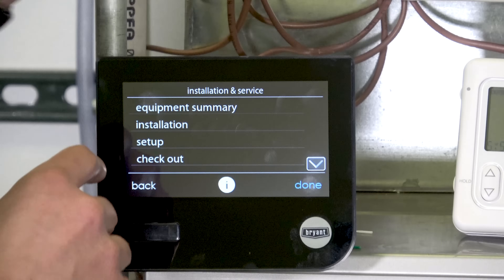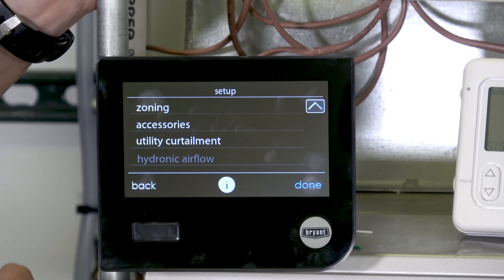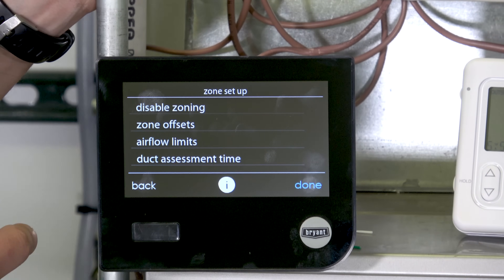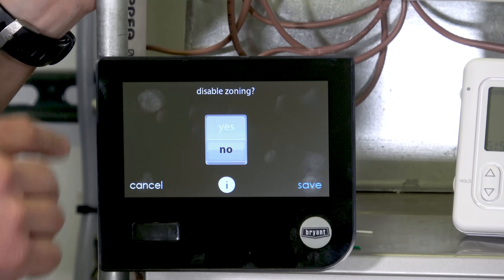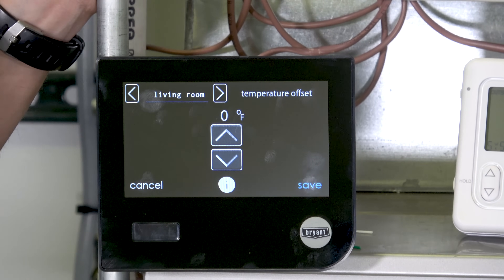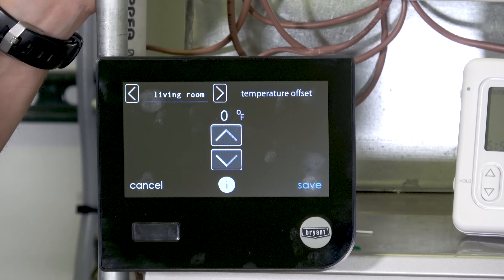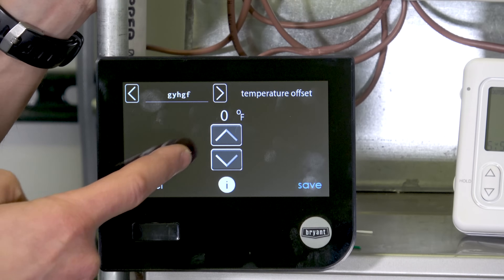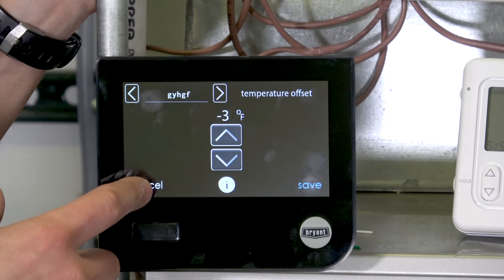In service settings, go to setup — thermostat, furnace, AC — and scroll down to find a zoning option. I can disable all zoning, for example in new construction before all the dampers are physically installed. I can also set zone offsets to calibrate the temperature sensors — add plus or minus five degrees to each zone to match a handheld monitor. With multiple zones I need this separate screen to handle all of them.